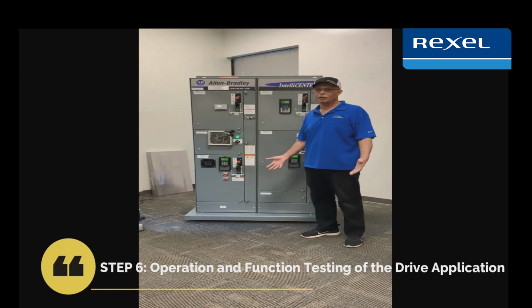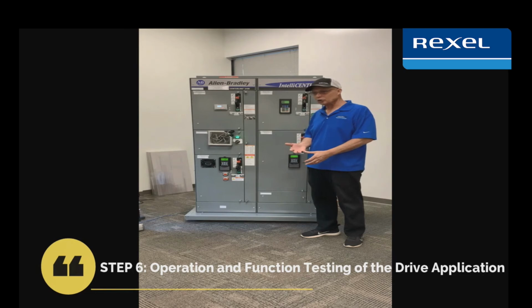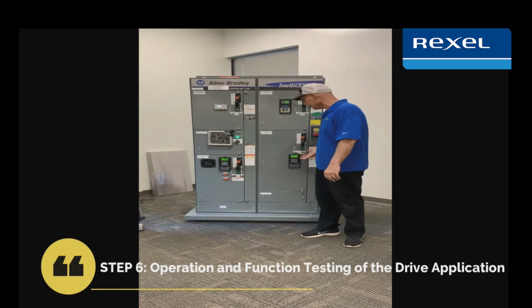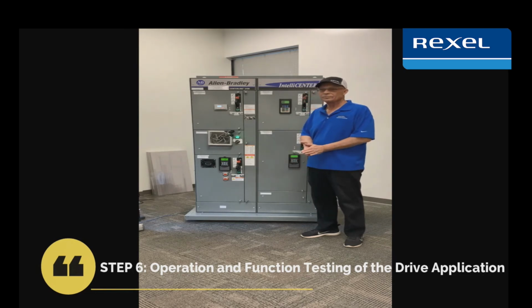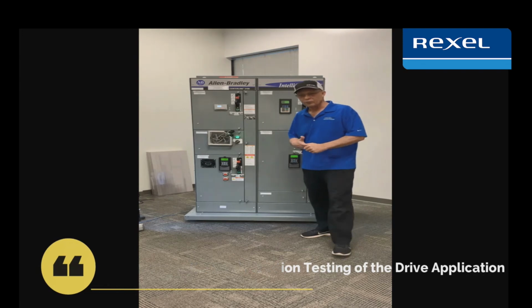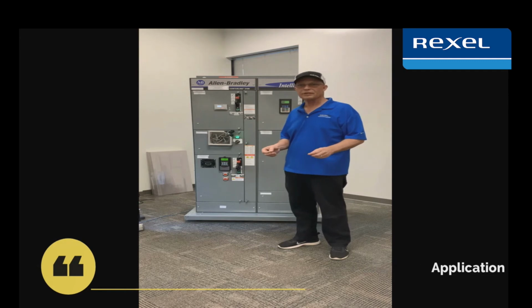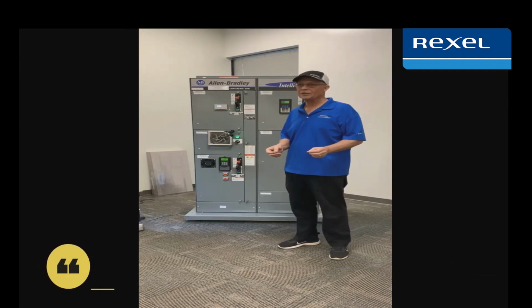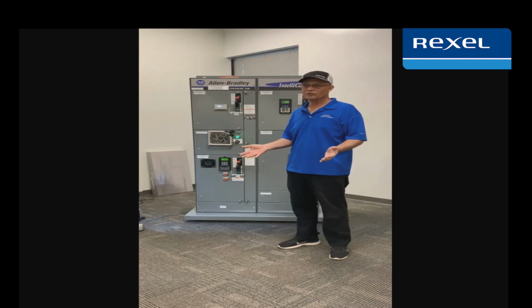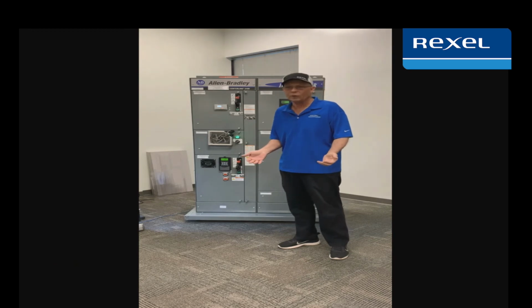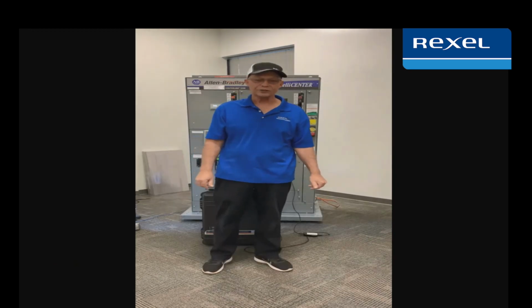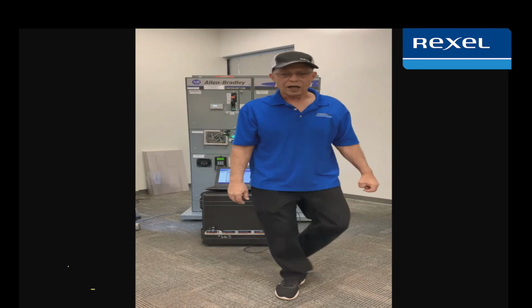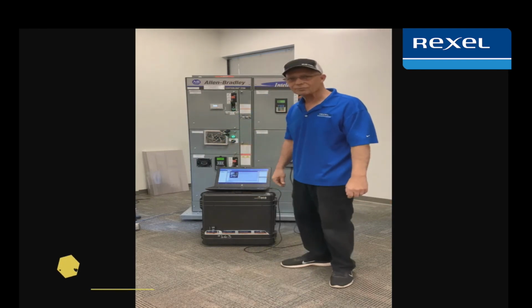Using CCW, I can data log and actually check the load on the motor. I can check it on the HIM, however, on the application of CCW, when I'm looking at it, I can review a millisecond in time. So I can actually see spikes, amp draw from starting over, let's say, a 20, 30 second up to maybe even a minute if I need to.